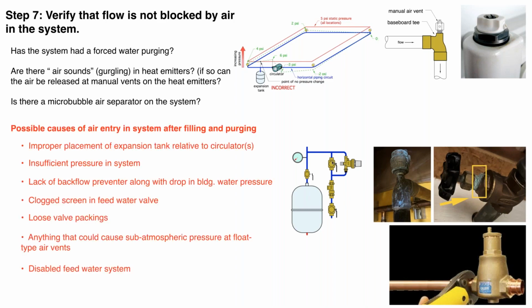So again, there's many possible causes that allow air to get in, okay? Improper placement of the expansion tank, low system pressure. If you let the pressure get too low, again, depending on how the circulator and the expansion tank are installed relative to each other, that just sets the stage to create these negative pressures and perhaps suck air back into the system. Lack of backflow preventer along with a building pressure drop. Without a backflow preventer, if the building pressure drops, the expansion tank is basically just going to push water back out, and that could cause a low pressure condition in the system. Clogged screen in the feed water valve, loose valve packings.